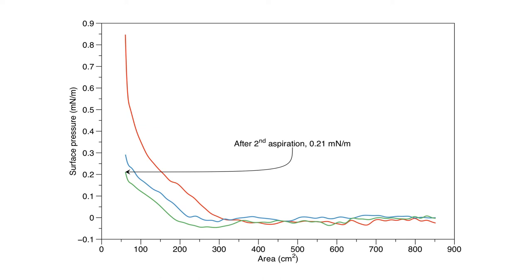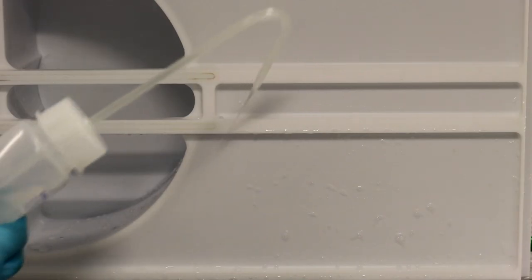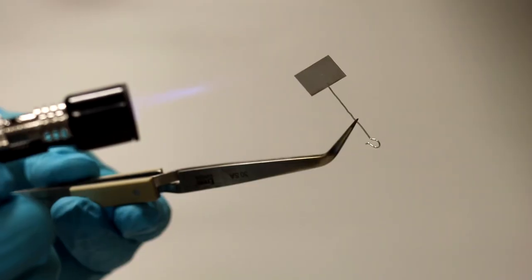If you are unable to satisfactorily reduce the change in surface pressure over the course of 3 to 5 compression and aspiration sequences, I'd recommend revisiting the trough, barrier and plate cleaning methods previously outlined.